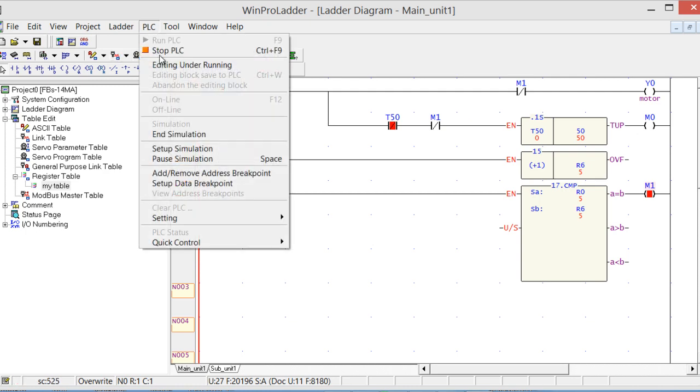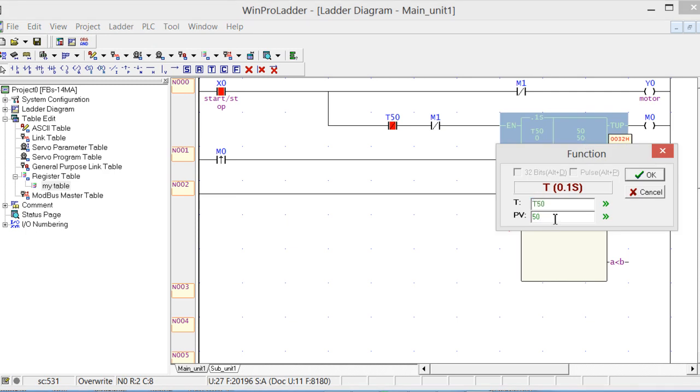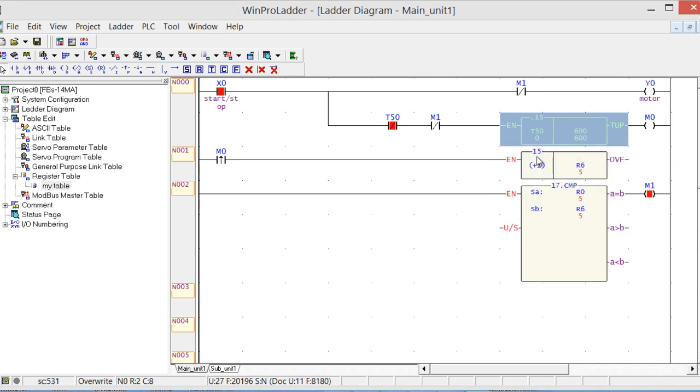OK, now stop. Now this value 50, once we know that our program is working perfectly, we can change this to 600. So now 600 equals 60 seconds. This will actually count minutes now. Our 5 is equal to 5 minutes. This value can be changed to 600 minutes or 60 minutes, 30 minutes, 15 minutes. This value can be then later on controlled from the SCADA. If we enter a value there, that value will be stored in R6, and in real time we can change the value.